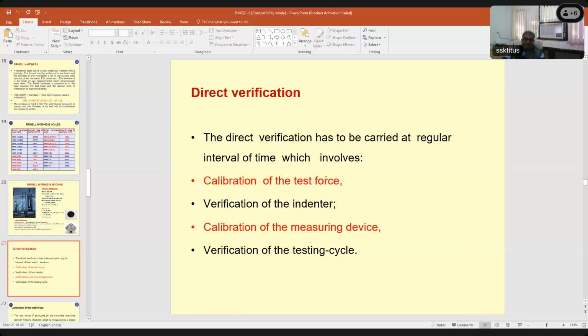Now, how to verify all these systems that we have established to generate these hardness scales? This is also very well defined in the standard, how the machine has to be verified. Because some of you may be calibrating your machines at your end. It requires direct verification and indirect verification. There are two methods which I slightly mentioned in the beginning itself. Both these things have to be done at a regular interval.